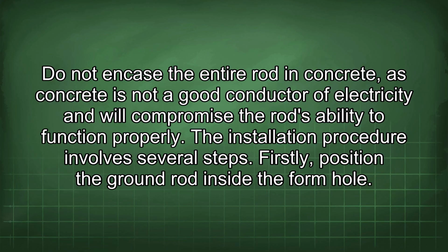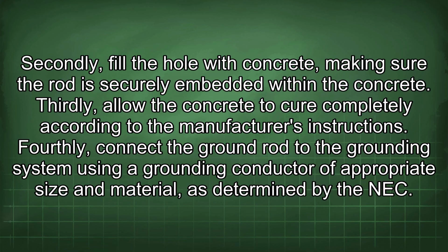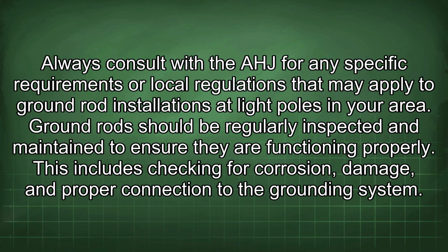The installation procedure involves several steps. Firstly, position the ground rod inside the form hole. Secondly, fill the hole with concrete, making sure the rod is securely embedded within the concrete. Thirdly, allow the concrete to cure completely according to the manufacturer's instructions. Fourthly, connect the ground rod to the grounding system using a grounding conductor of appropriate size and material as determined by the NEC. Always consult with the AHJ for any specific requirements or local regulations that may apply to ground rod installations at light poles in your area.